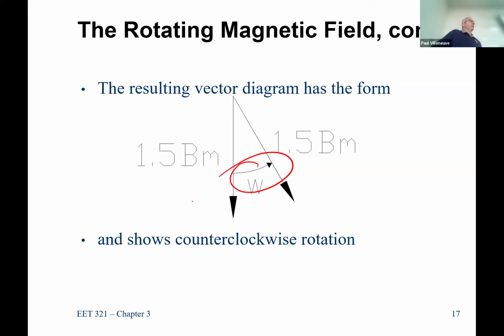And if you plug it in and you turn it on and it's rotating clockwise, then you might have damaged the mechanical system. So by decoupling the mechanical load from the electrical motor, you bump it, you just energize it for a second, you watch the motor spin and verify, does it flow in the proper direction or the improper direction? If it's flowing in the improper direction, you de-energize, you swap any two leads, and then you bump it again and you'll see it switches direction. So you can get reverse or forward direction literally by swapping any two phases. Super, super easy to do.